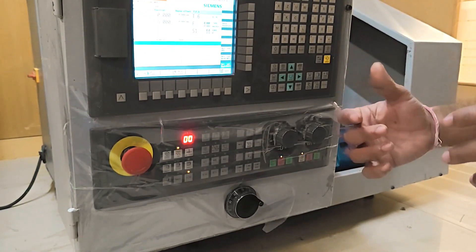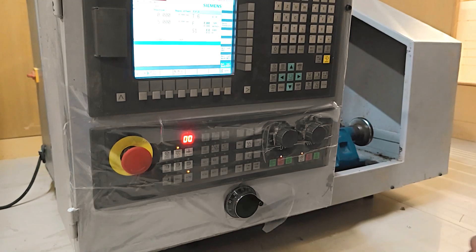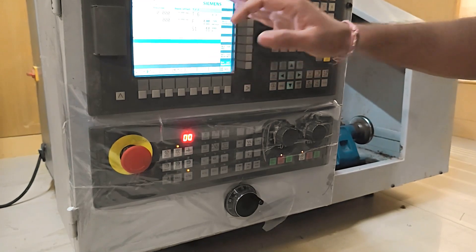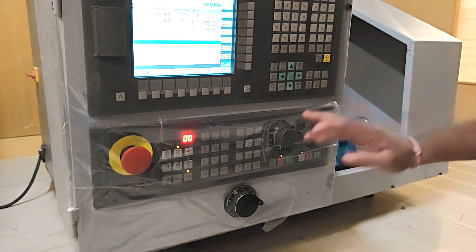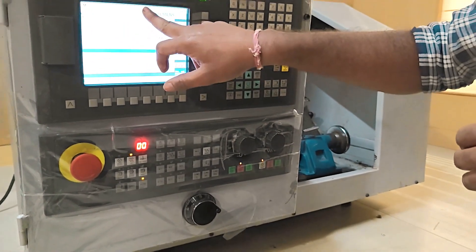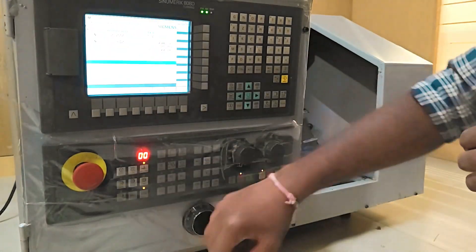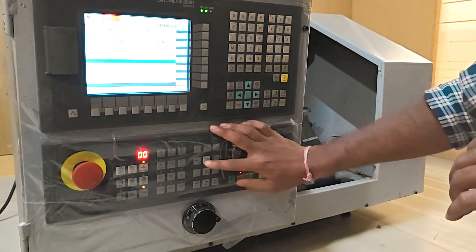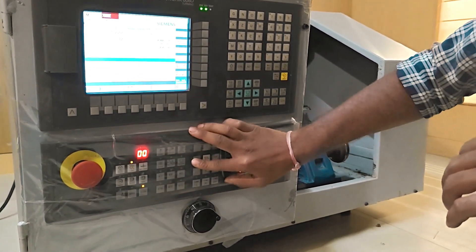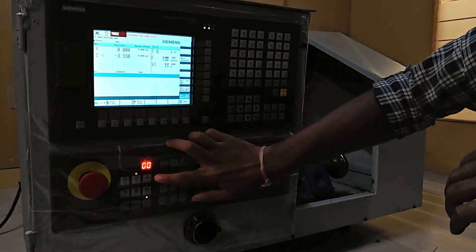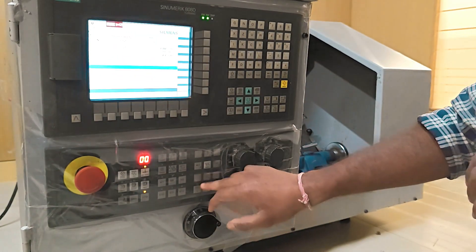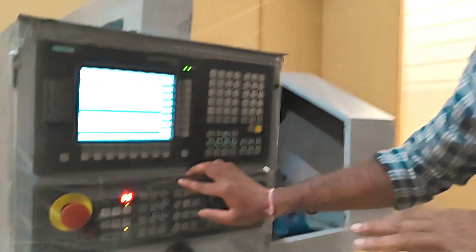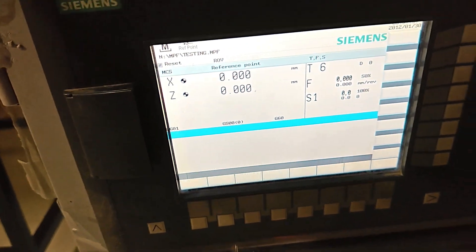The NC has a software limit set — for example, Z-axis plus five. If you have exceeded the software limit, you can jog back within the limit on the Z-axis. Once you press reference and Z-plus, it will automatically go to the home position and the display will show 0-0, meaning it is in the reference position.